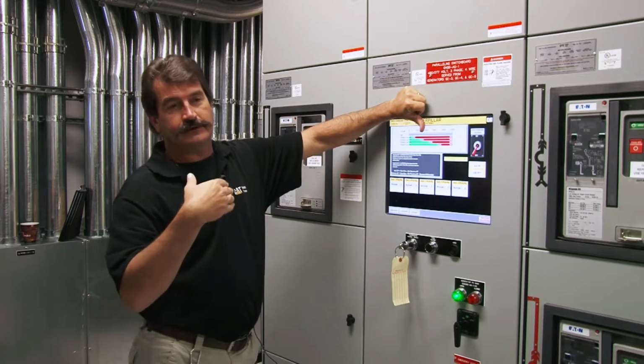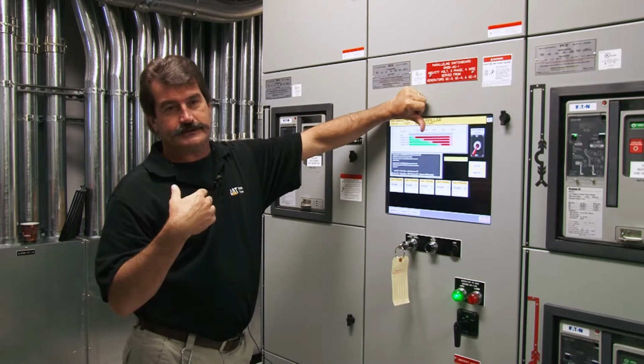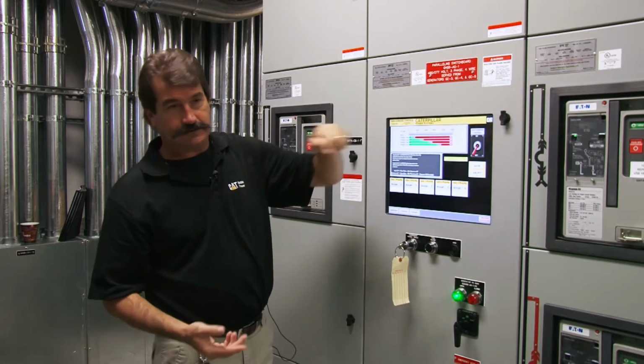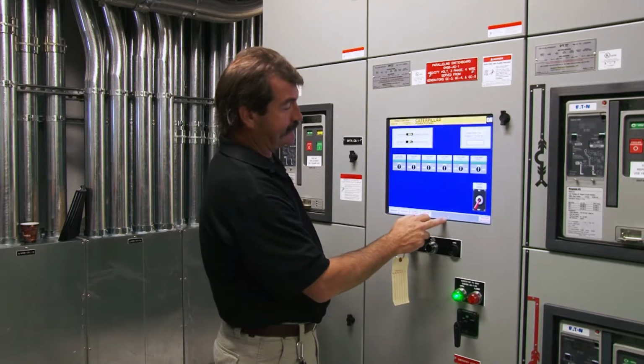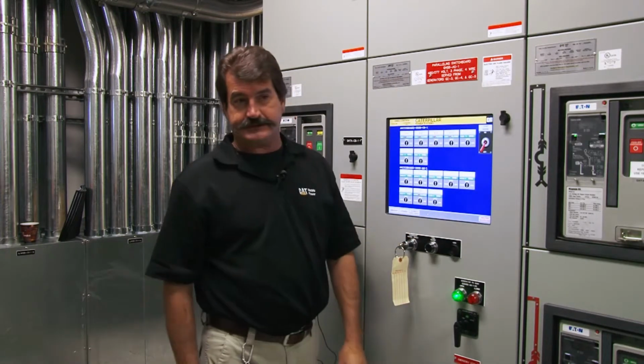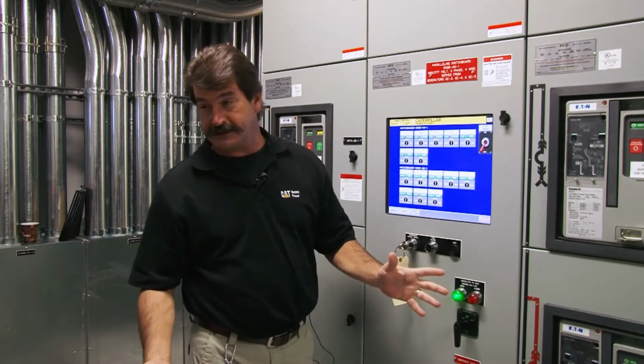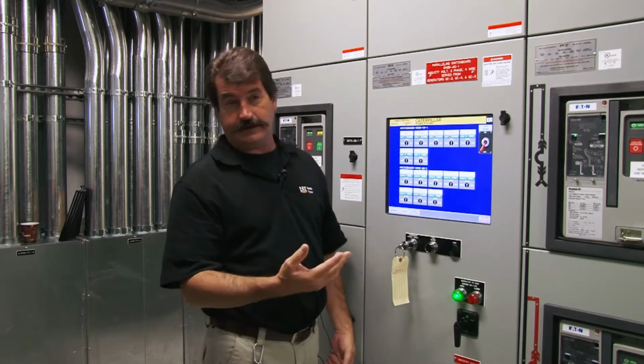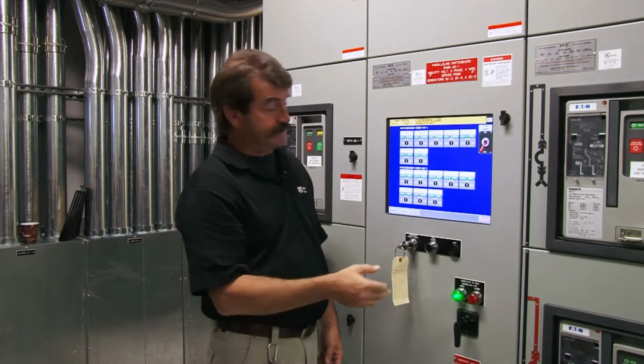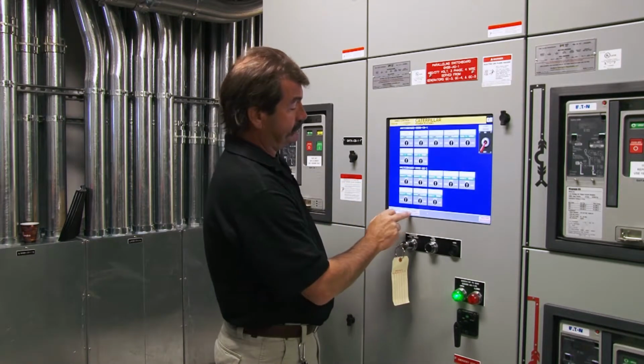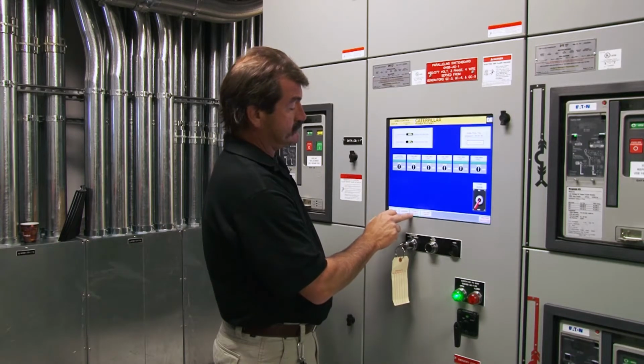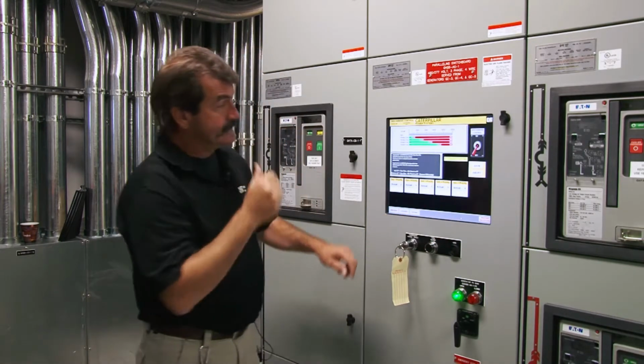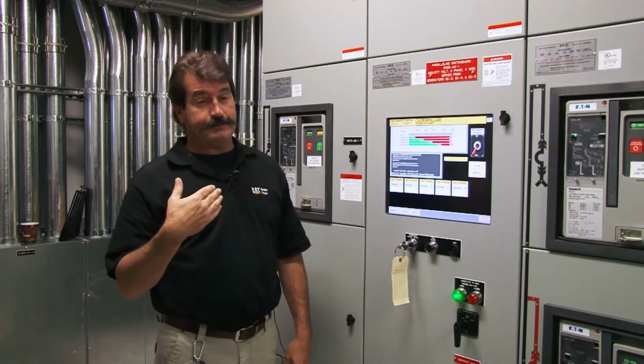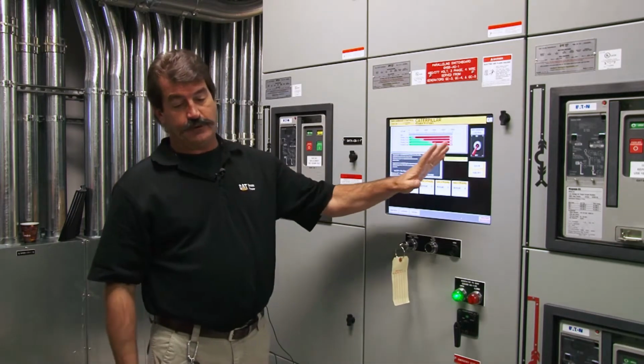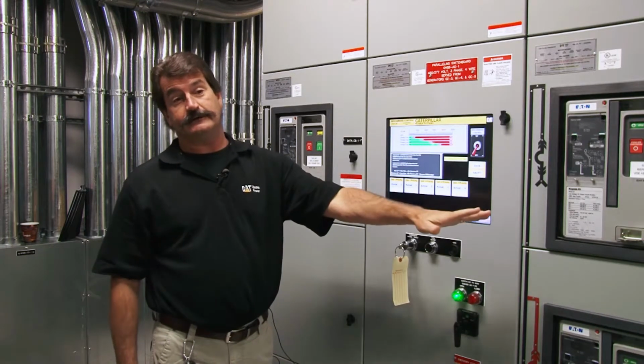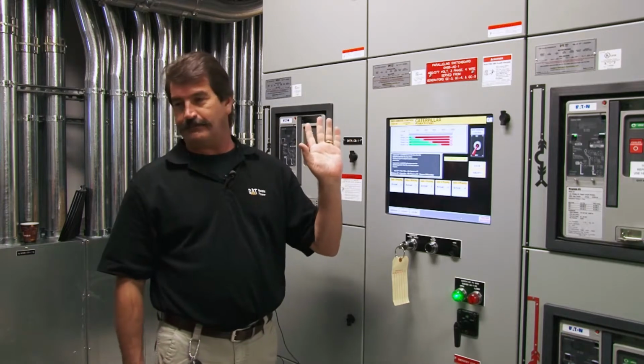But then they would close back in after a certain amount of time, because the only way to get that to work is you have to have your load sense, okay? And it actually should say load sensitive. Your load sensitive has to be on before your gen demand can be on, okay? System control, gen demand, okay. So yeah, it'll pop open your priority 5 breakers, and then it'll close them in after it looks at load and says, oh no, we got plenty of load.